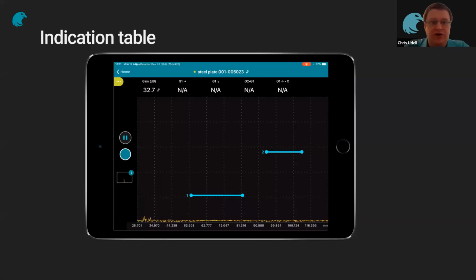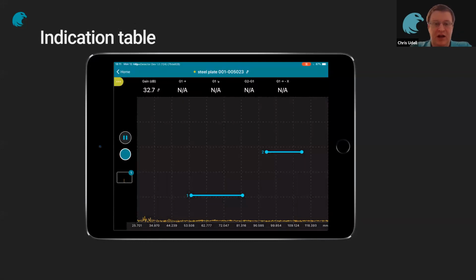In addition, we've also got an indication table. This is a great feature from phased array, which is missing on the conventional ultrasonic flaw detectors, because reporting is just as important in manual UT as it is in phased array. You can see here that I can add an indication. So I'm going to get the peak of that, press record.